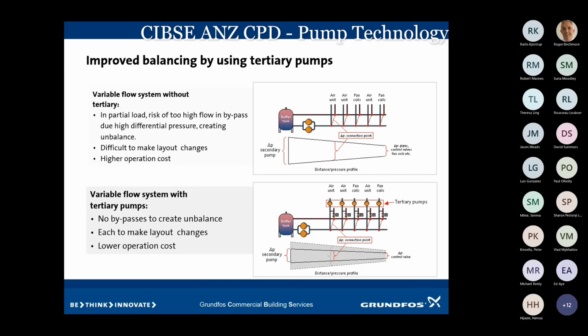Whereas the variable flow system below is very good for pump sales because there's more pumps, but there is a bonus. There's some energy savings and better control. You can see now at the buffer tank, the pressure that's required for the primary pump is a lot lower. The primary pump is only pushing the water through the loop, and then at each air handler or fan coil, we've got individual pumps that are managing those by themselves, and so they're much smaller. All they're doing is drawing water off that primary loop, and they're controlling themselves more individually. So as each one of these units changes, that pump can change with it. It's not just one big pump having to try and manage all the little pumps at the same time.